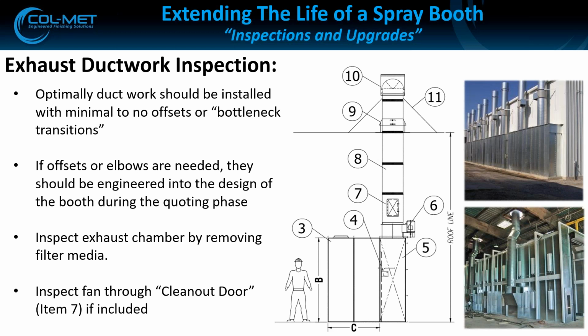they want to move, right? So you have some older equipment and we're looking to move it to a newer facility or across the plant. When they were originally designed, the ductwork was very streamlined, right? Maybe it had one offset, like our picture to the right, just that one offset in the ductwork. Everything is at least three diameters away from the fan, so we know that we're getting good laminar airflow.